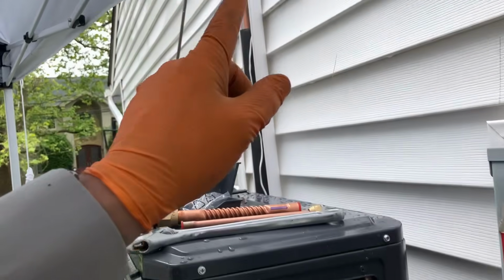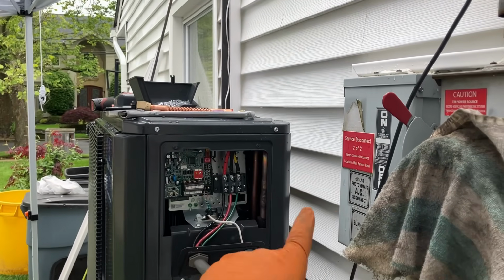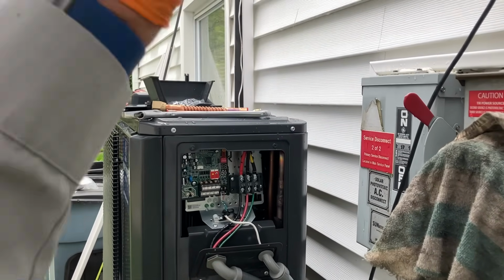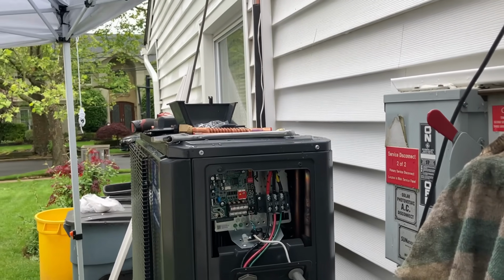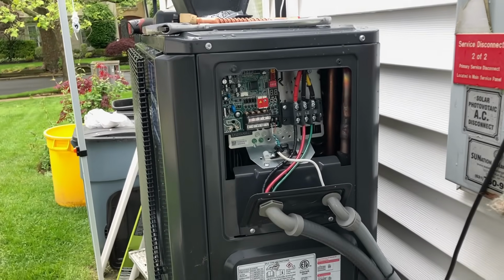We're going to connect the 3/8, make that up. That's not tight, by the way. We're going to make up the 3/8, and then we're going to use the pipe wiper to flush out the line of all the R22 oils.